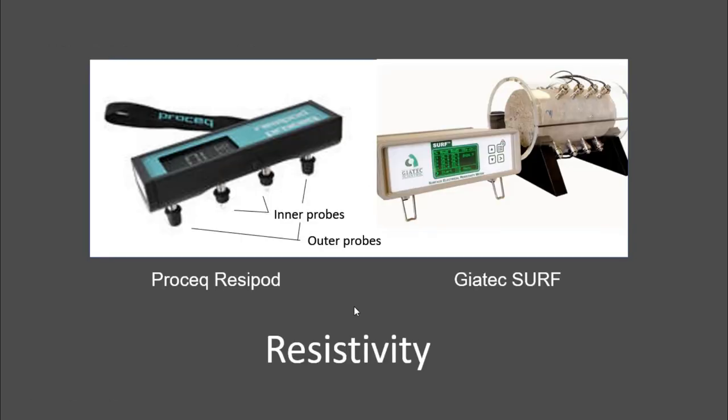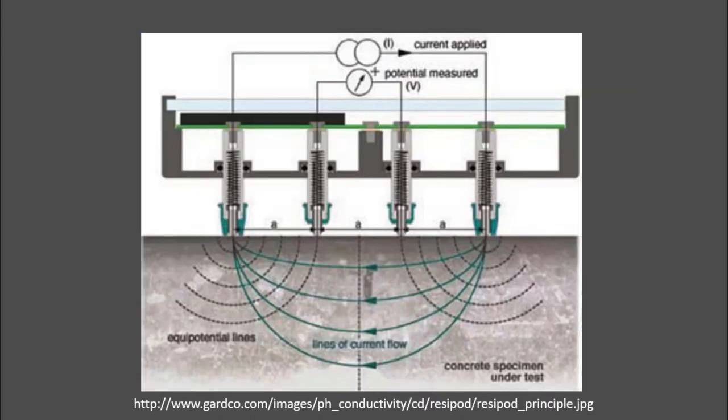And one of the great ways to do that is with resistivity. I'm showing two different commercially available devices here that can measure resistivity and they're pretty simple. You put them on the concrete and there's a current that's sent from one side to another and you actually measure the potential or the voltage across the middle two probes.